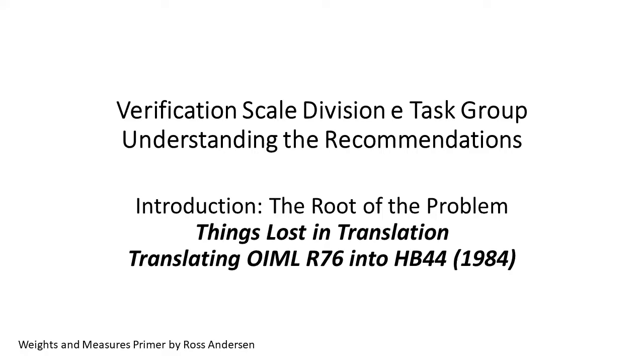The pre-1984 scales code, written originally for analog instruments, was woefully incapable of handling the demands of digital electronic weighing instruments. The international community had a code. The international approach varied diametrically from the old code, as I shall explain. The decision was not to repair, but to repeal and replace the old code, moving mostly to the R-76 approach. There were obstacles the translators had to overcome. Simply stated, R-76 had to be translated into Handbook 44. The confusion stems from what got lost in translation.